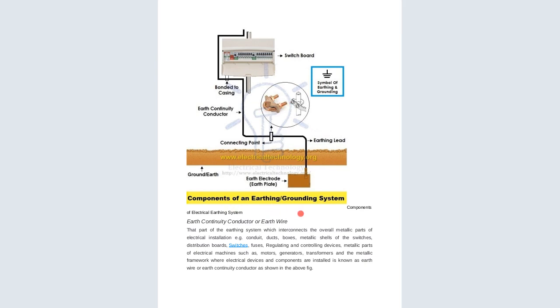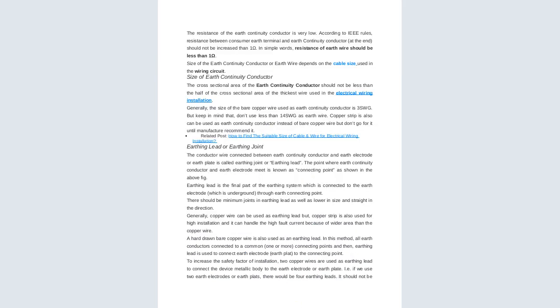So, the components of the earthing and grounding system. The continuity earth conductor, or earth wire, is a part of the earthing system which interconnects the overall metallic parts of the electrical installation, e.g. the conduits, ducts, boxes, metal shells of switches, distribution boards, fuses, regulating and controlling devices, metallic parts of electrical machines such as motors, generators, and transformers, and the metallic framework where electrical devices and components are installed. It is known as the earth wire or electrical continuity conductor, as shown in the figure. You can see it in the figure above. The resistance of the earth continuity conductor is very low, according to the IEE rules.